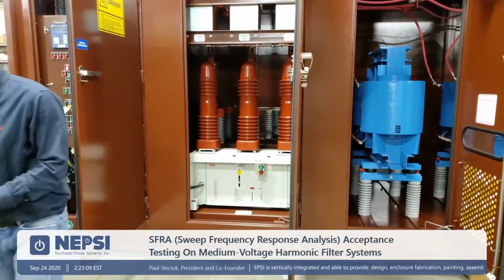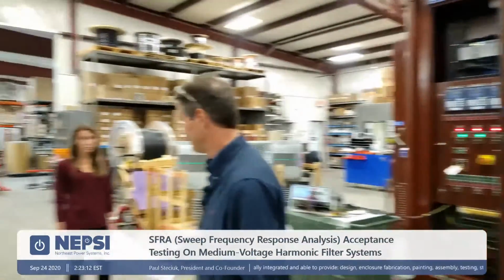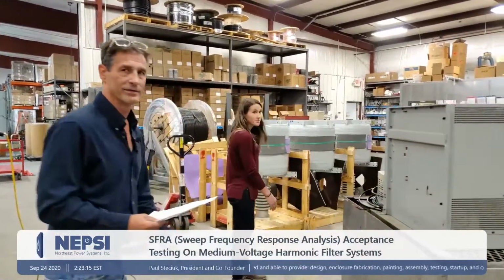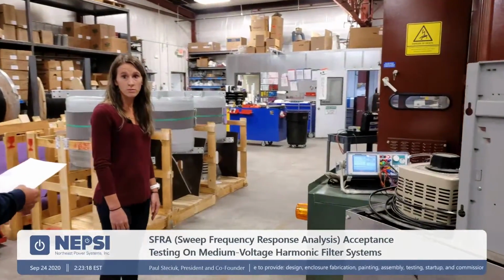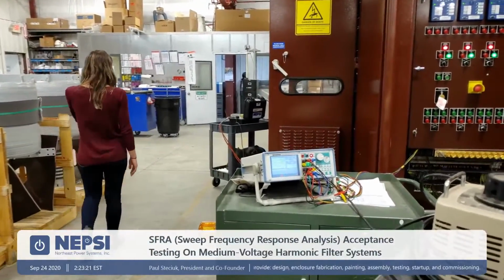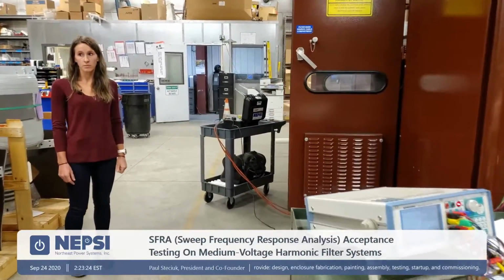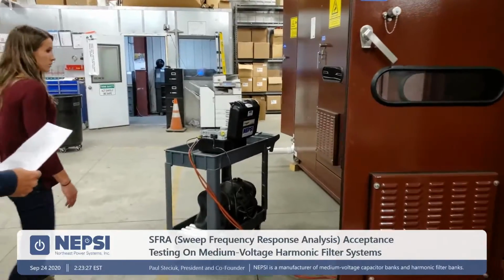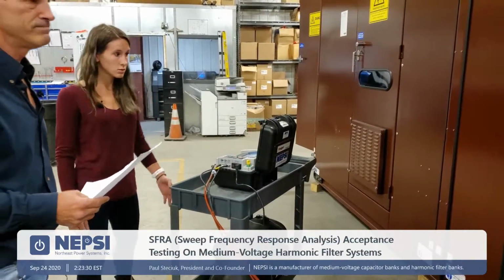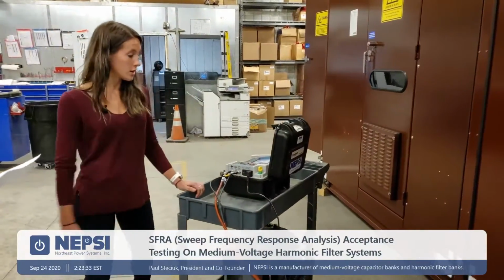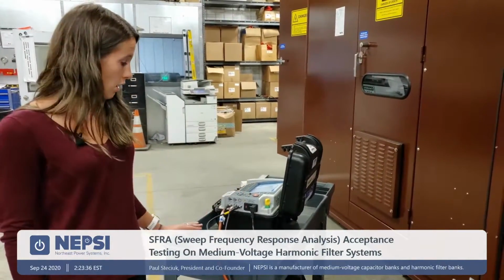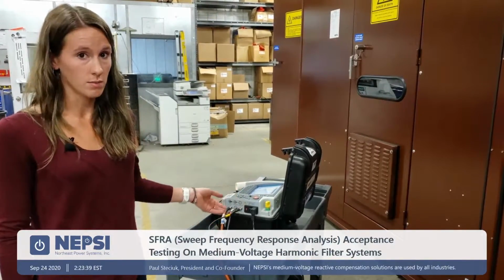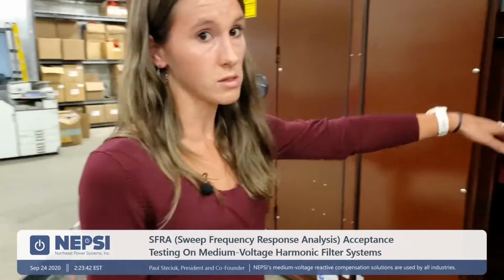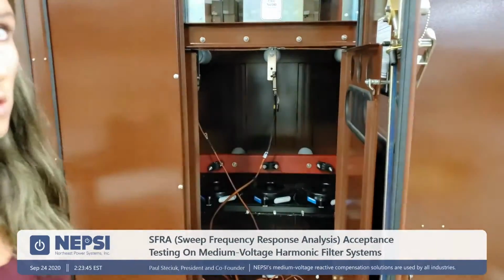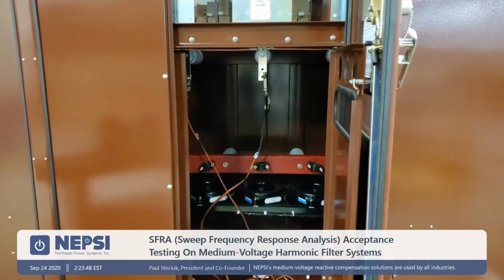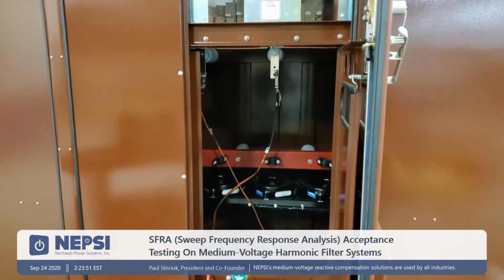So for this, Jess is mainly involved in the testing that requires a lot of technical background. So she's actually in charge of impulse testing, partial discharge testing, and the SFRA. So Jess, why don't you show this connection that you make, please. Yes. So for the SFRA, we use the Megger FRAX 150. There's a generator lead, and then there's the measurement lead, and we connect those from phase to phase. So we'll do A to B, B to C, and then A to C. And those are right in there. They're on the incoming bus, so where the customer would connect their source.